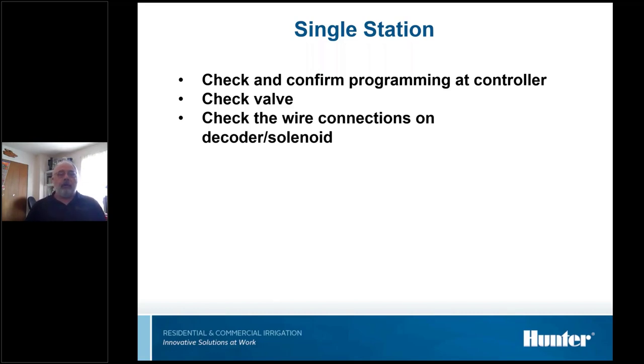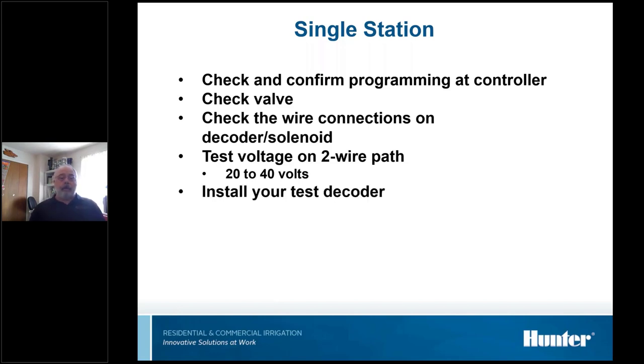If you've got a single station that doesn't work, I literally go to that valve box, grab hold of the decoder, and pull and see what wants to come apart. Most of the problems we find are connections that have fallen apart or weren't made right to begin with. But that's the first thing you do: yank and pull on the connectors, make sure everything's all good. And if it is, then we can test voltage on the two-wire path, make sure we've got voltage coming into the decoder. Should be in this range. When you get way out on a wire path, you could see voltages as low as 20 volts. That's usually telling you there's something up if it's that low, unless you're on a two-mile-long path.